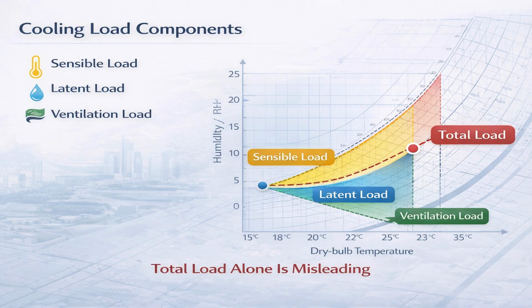One of the most important things to understand in HVAC design is that cooling load is not a single number. Cooling load is made up of different components, and each one behaves differently. Sensible heat affects air temperature, latent heat affects humidity and moisture levels, and ventilation load introduces both heat and moisture into the space, especially in hot and humid climates. Different HVAC systems and even different unit configurations handle these components in very different ways. Some systems are better at temperature control, others are more effective at moisture removal. And ventilation loads often require dedicated strategies.